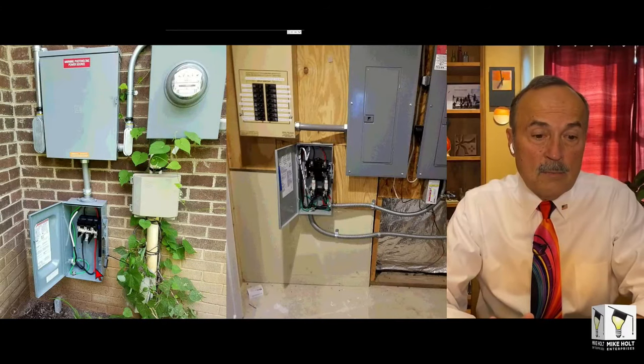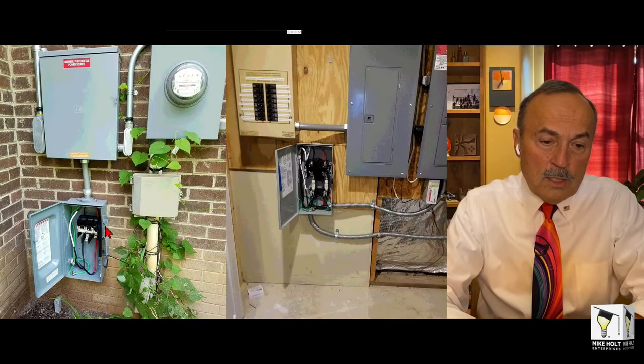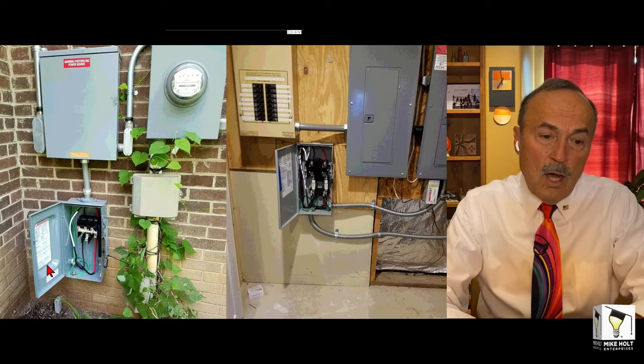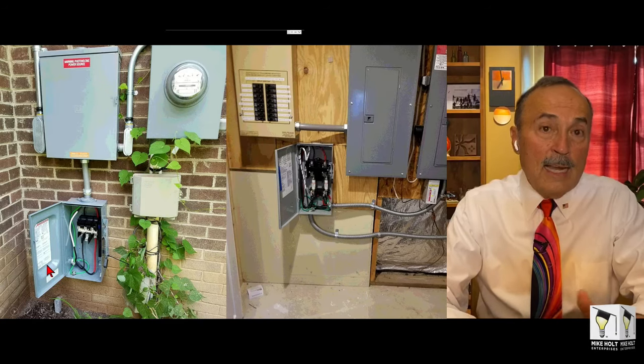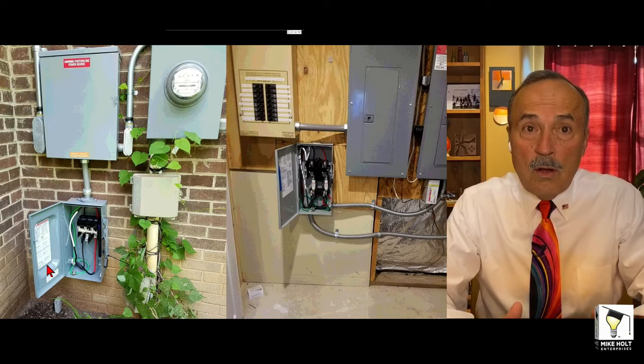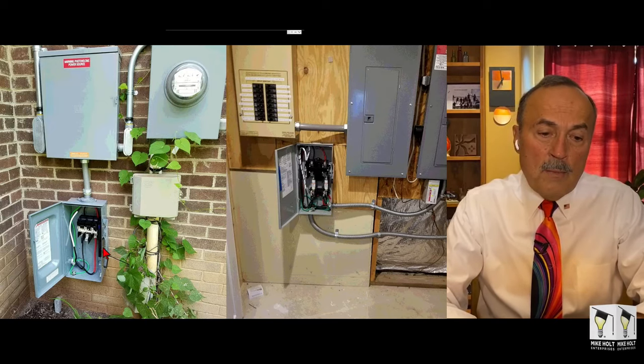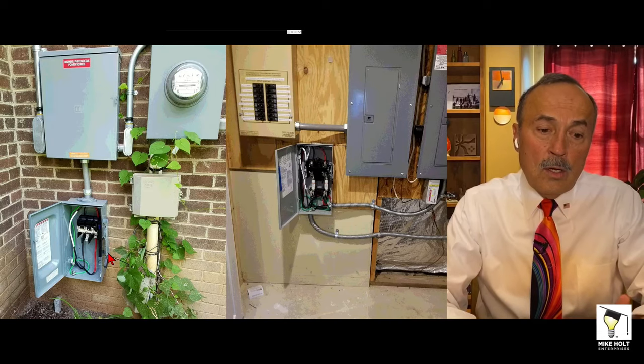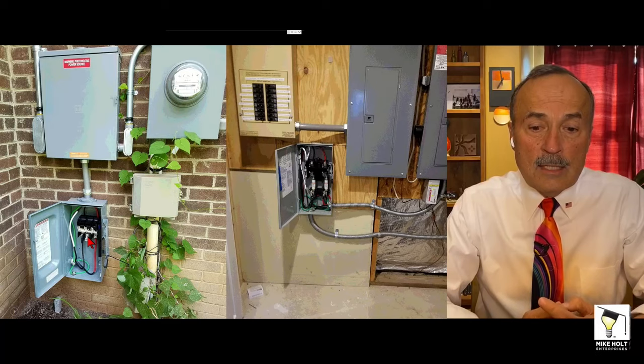So let me just kind of talk about what the scenario is, and then we'll play that video in a second. This happens to be a PV system. And you can see, here's the earth right here, so you can see that this disconnect is pretty low, which is fine. The code doesn't have a minimum height for a disconnecting means. But the way this cover works is you turn the disconnect off and that cover opens up. I never really gave this a consideration or a thought at all. And he's saying, well, the problem with this is a child can go here, turn that disconnect off, open this cover, and get access to energized parts.